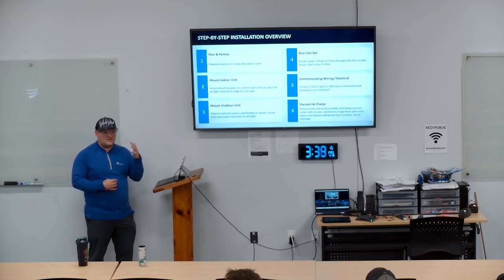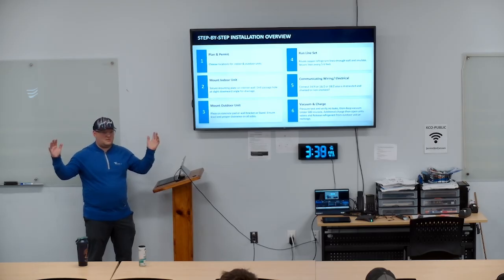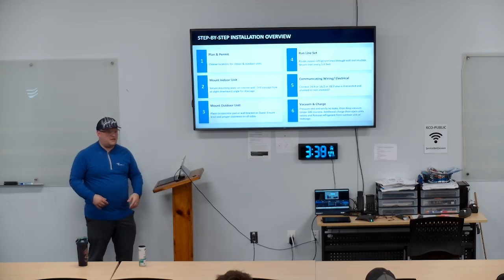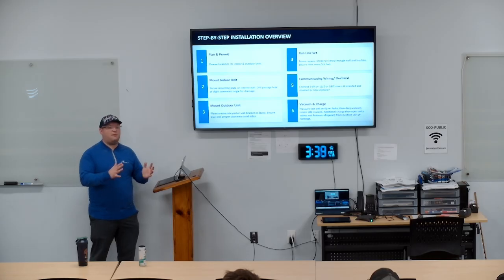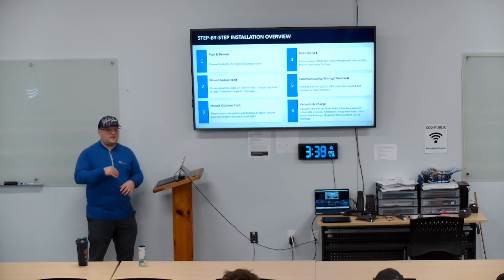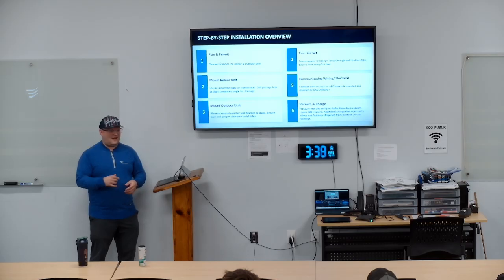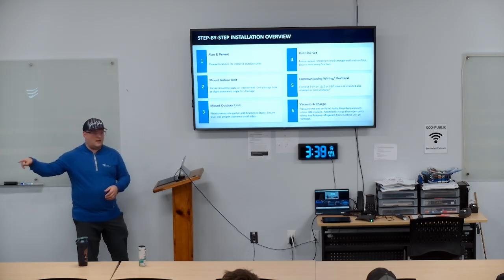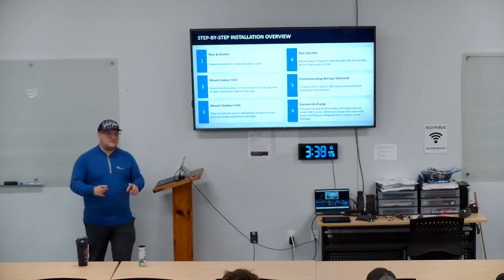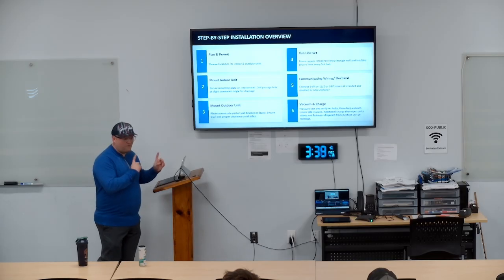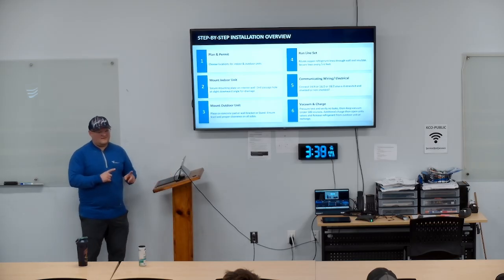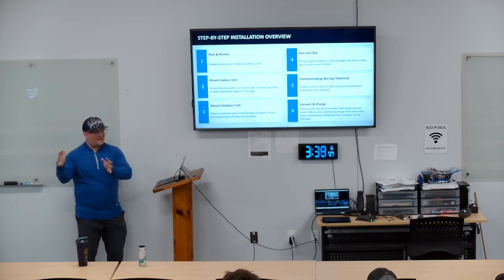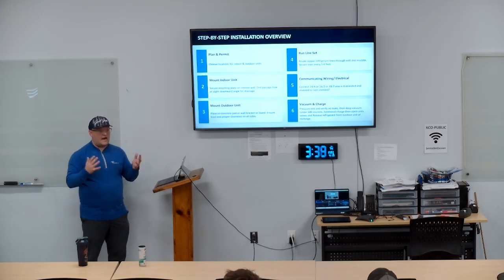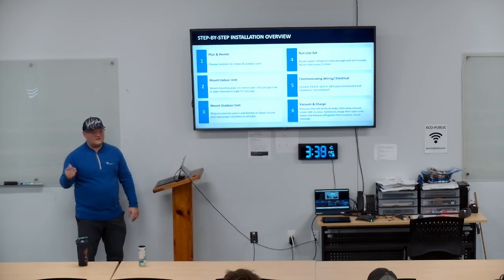Because I've spent 4 or 5 days straight looking for a pinhole leak in a 3/8 line with 6,000 feet of copper in this building. And everybody's wanting to jump because it's like, I don't know where this freaking thing is. We lost 10 pounds overnight. Well, maybe it's not a leak. Okay, well, let's leave it one more day. Come back next day. Another 15 pounds down. And I found a pinhole leak 5 floors away off a branch box. That was a connection that was from the factory. Right? But if I would have pressure tested that ahead of time, in sections, I'd have known, hey, that ain't holding.